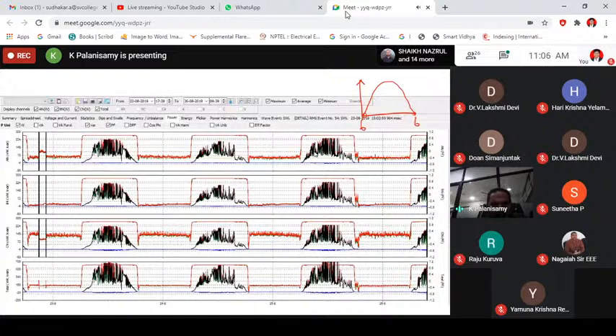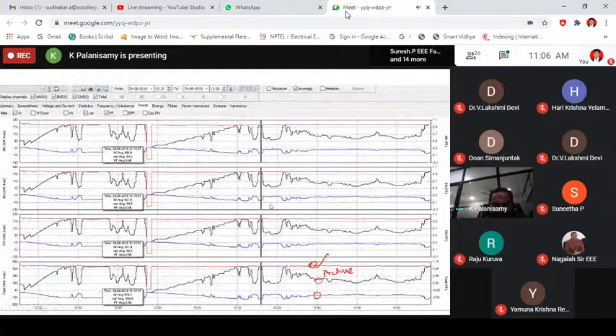And this was the measurement data taken by me from one of the plants. You can see this is what I was talking about, right? The solar generation is something like this. It is highly varying. It's not a smooth sinusoidal waveform from 6 a.m. to 6 p.m. It is highly varying. This is the expanded version of that. You can see how it is varying. All of a sudden, from 600 kilowatt it comes down to 400 or 200 kilowatt. So that is a 400 kilowatt variation from one particular plant.